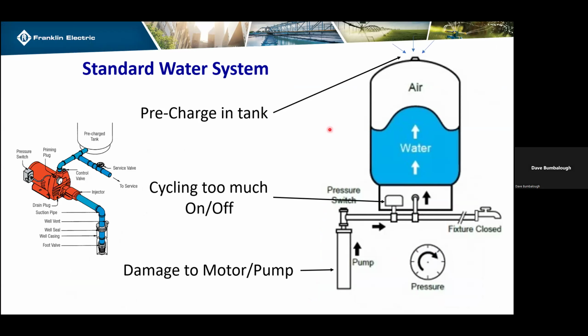A lot of times the end user does not realize that we've lost a little air and we need to add back that air to ensure that cycling doesn't occur and that the system runs flawlessly. So just as an FYI, those are some things that can cause the motor to twitch in the well, constantly start and stop, which can cause the motor windings inside to short to the shell, hence the leakage voltage.